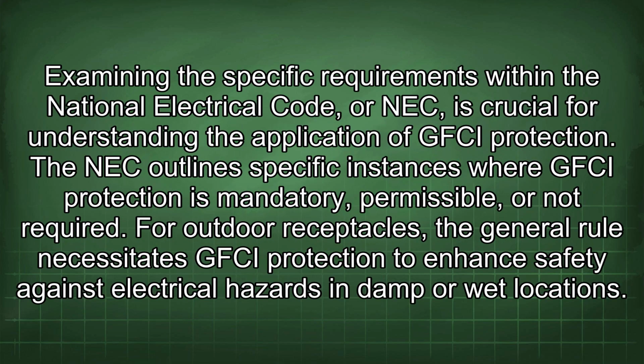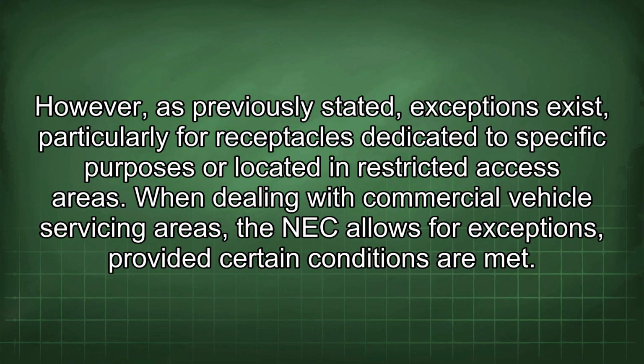Examining the specific requirements within the National Electrical Code, or NEC, is crucial for understanding the application of GFCI protection. The NEC outlines specific instances where GFCI protection is mandatory, permissible, or not required. For outdoor receptacles, the general rule necessitates GFCI protection to enhance safety against electrical hazards in damp or wet locations. However, as previously stated, exceptions exist, particularly for receptacles dedicated to specific purposes or located in restricted access areas.